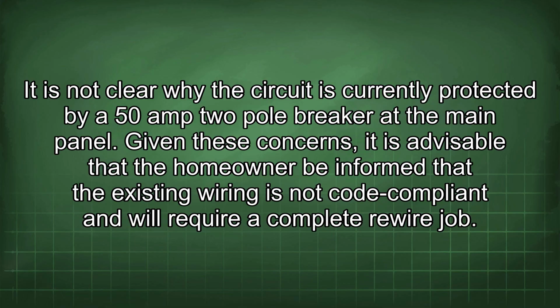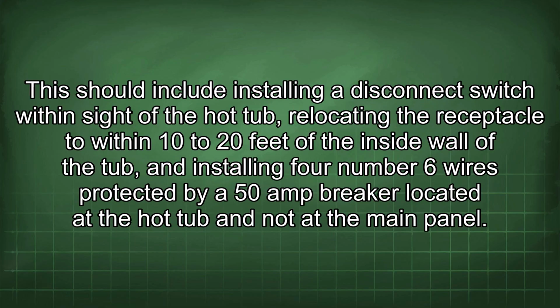Given these concerns, it is advisable that the homeowner be informed that the existing wiring is not code compliant and will require a complete rewire job. This should include installing a disconnect switch within sight of the hot tub, relocating the receptacle to within 10 to 20 feet of the inside wall of the tub, and installing 4 number 6 wires protected by a 50 amp breaker located at the hot tub and not at the main panel.